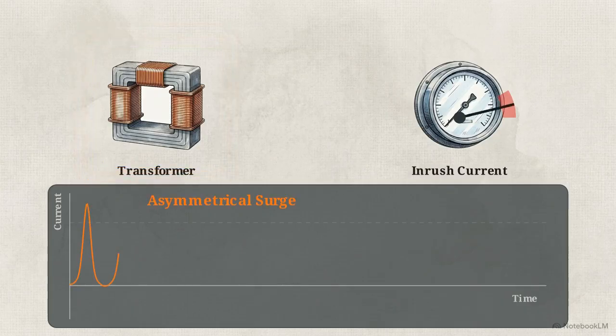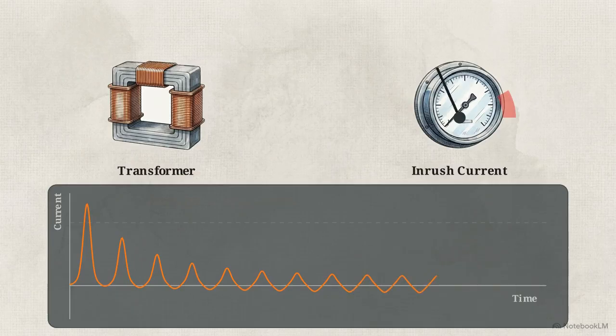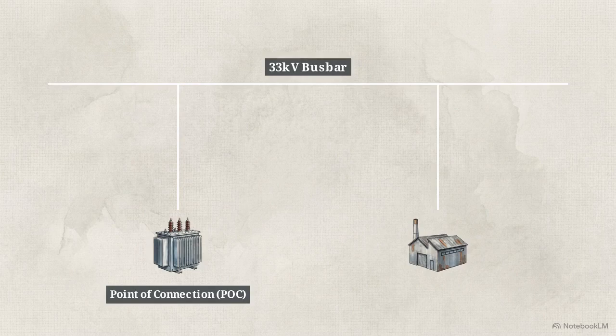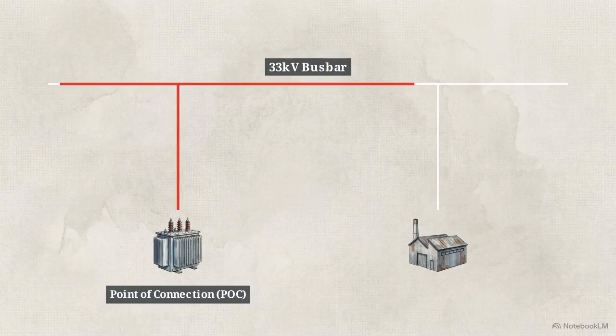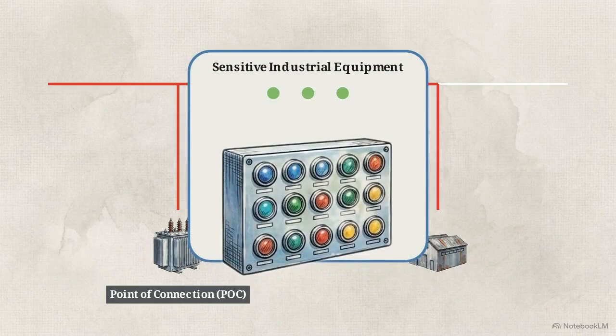At the exact moment a transformer is energized, it can draw an asymmetrical surge of current that significantly exceeds its normal operating load. Because the grid has a finite short-circuit capacity, this sudden, massive draw of current creates a rapid, localized drop in voltage at the point of connection. This voltage sag doesn't stay isolated.